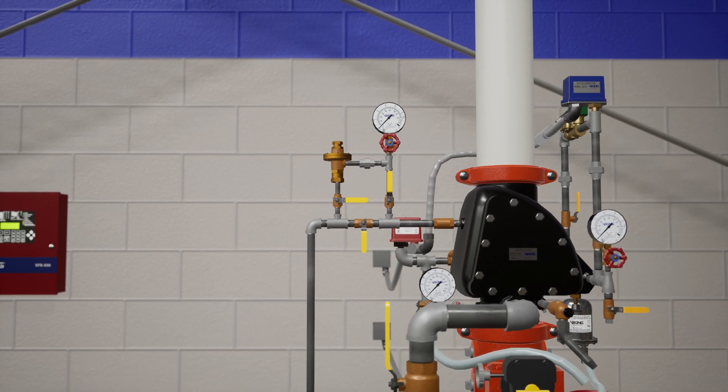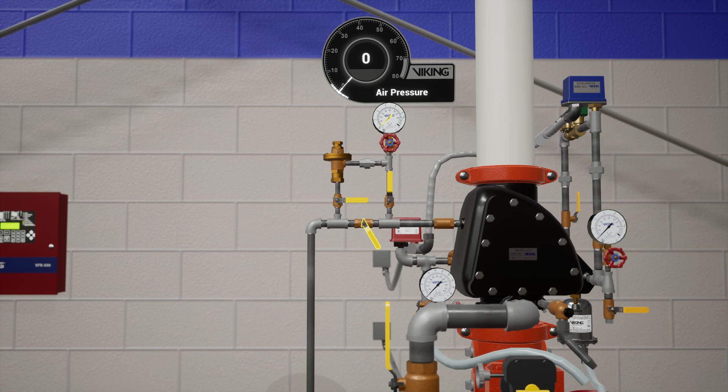Next, reestablish the system air pressure within 5 psi of the set pressure by opening the air bypass valve. Once pressure has been reestablished, close the air bypass valve.